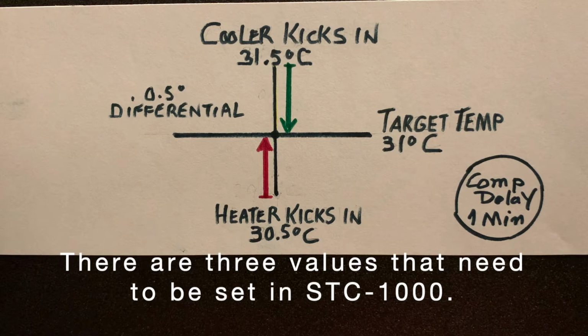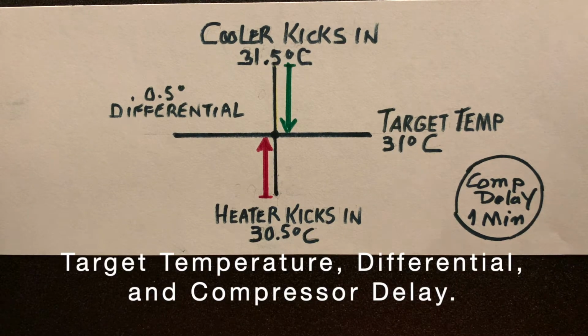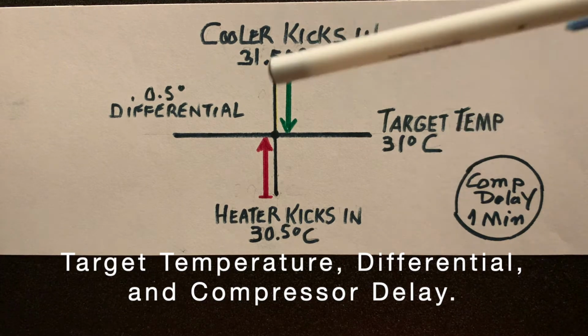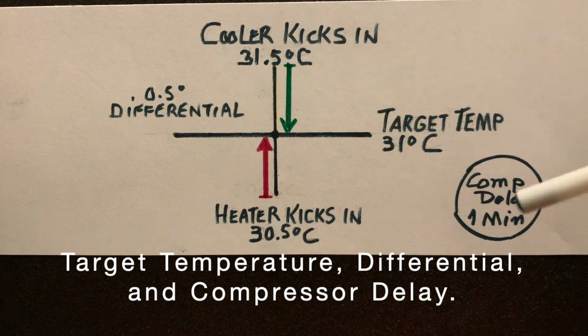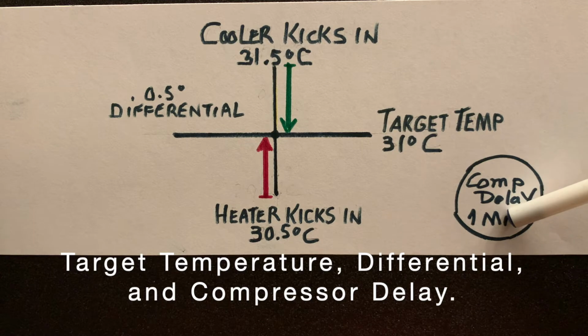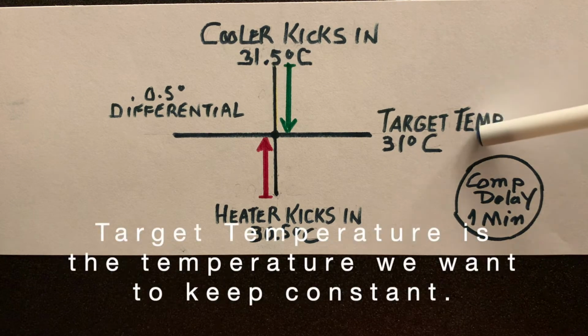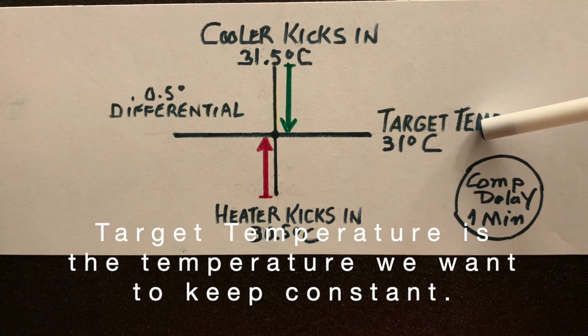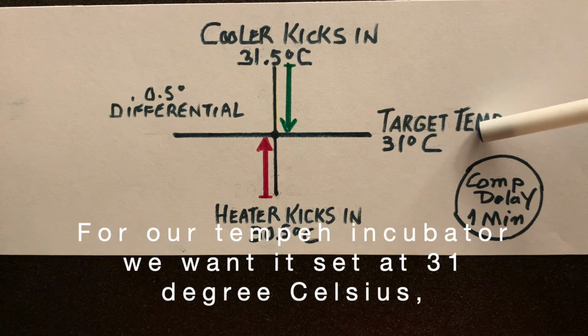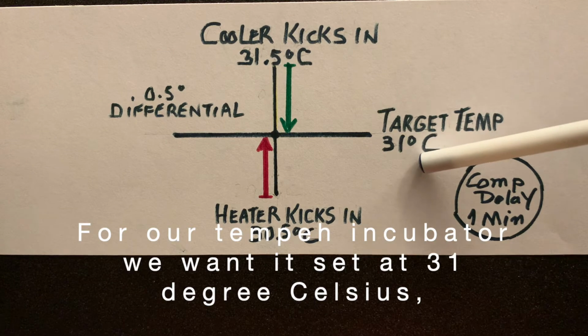There are three values that need to be set in STC1000. Target temperature, differentials, and compressor delay. Target temperature is the temperature we want to keep constant. For our Tempeh incubator, we want it set at 31 degrees C.